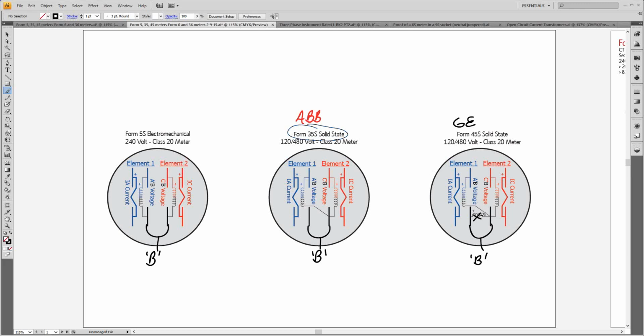Then back to the idea, if I would put a new one of these in, all of these are for three-phase 3-wire delta, and I'll show you a diagram here in a second. All of these are on the same one. If this jumper sits in place and I'm going to install a new one, I really only have to put B phase to this terminal, because I don't have to have it here to null this one out. I just have to make sure that B phase is on the opposite side of that potential coil, and on the opposite side of this potential coil.